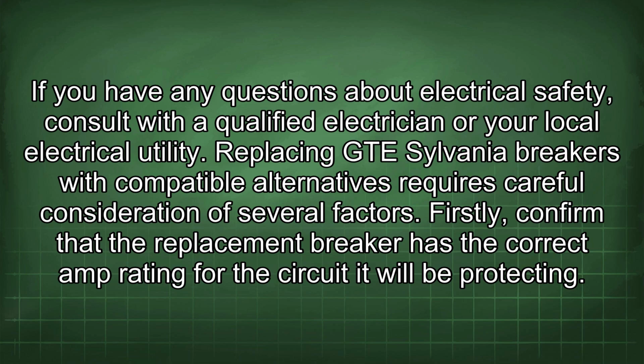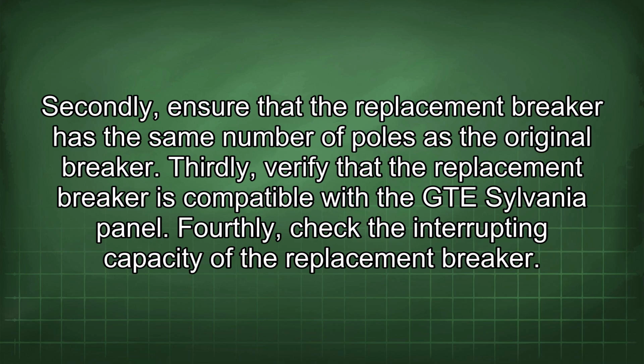Replacing GTE Sylvania breakers with compatible alternatives requires careful consideration of several factors. Firstly, confirm that the replacement breaker has the correct amp rating for the circuit it will be protecting. Secondly, ensure that the replacement breaker has the same number of poles as the original breaker. Thirdly, verify that the replacement breaker is compatible with the GTE Sylvania panel. Fourthly, check the interrupting capacity of the replacement breaker.